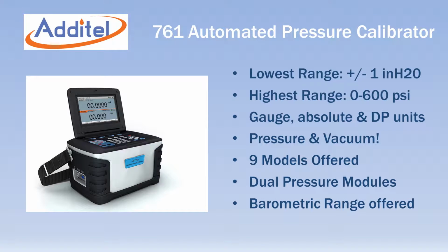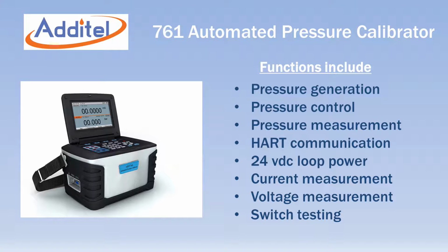When I saw this sitting on the table, I'm looking under the table for the rest of the stuff. Where's your gas supply? Where's your pressure supply for this? How can you generate? At the time it was 375 psi is what Additel was doing with this product. And so it was amazing to me. I mean, it's an engineering marvel. I agree. In my mind. And so we've got a range, from low inches of water, down to plus or minus 1 inch of water, all the way up to 600 psi. And each one has 2 sensors built into it. Basically, a documenting process calibrator is built into the guts of this device, where you can document, you can do process instrumentation, you can do general gauges or kind of whatever.